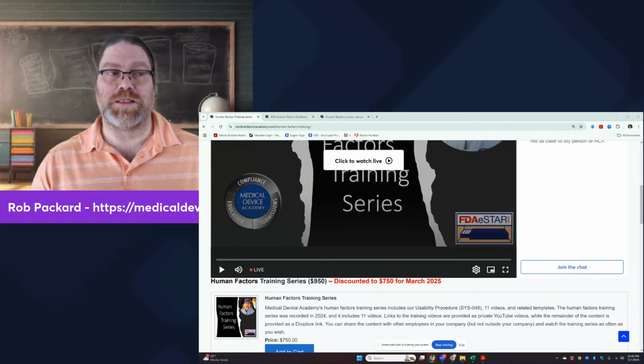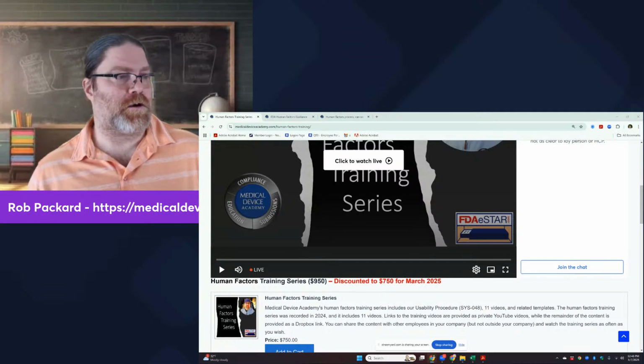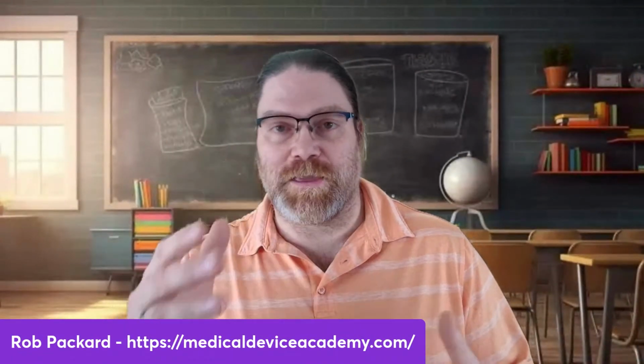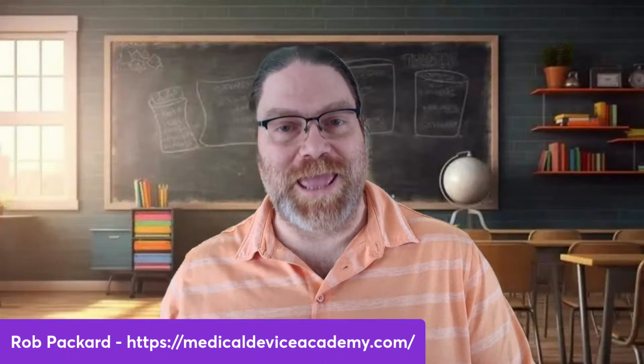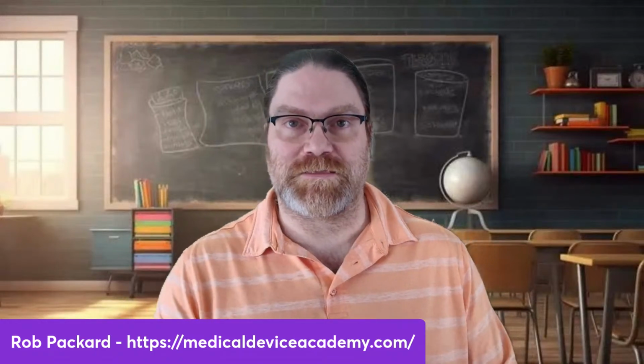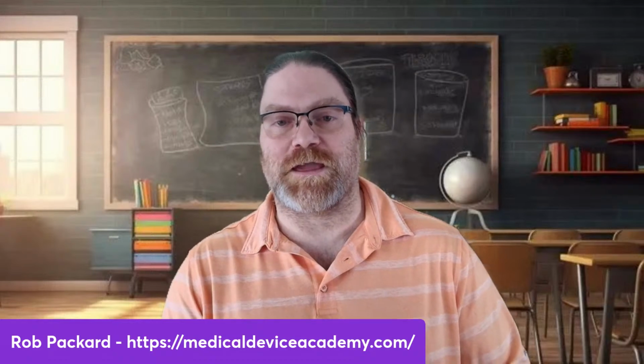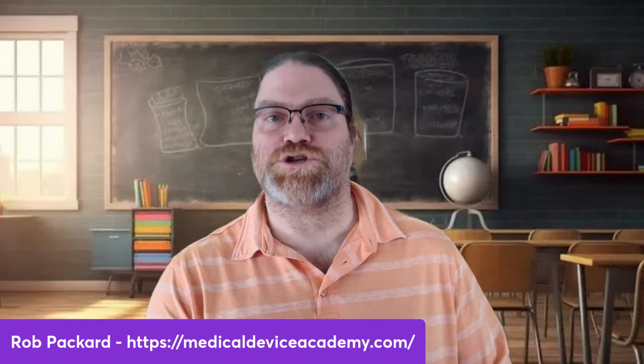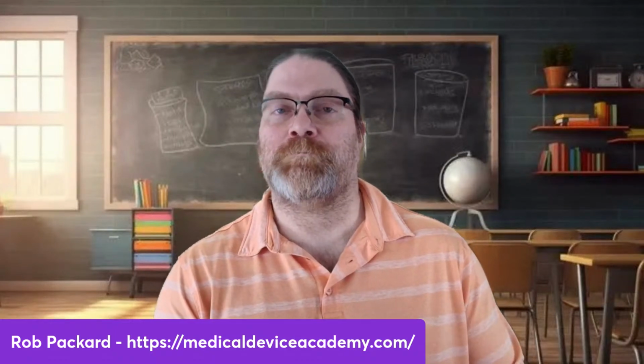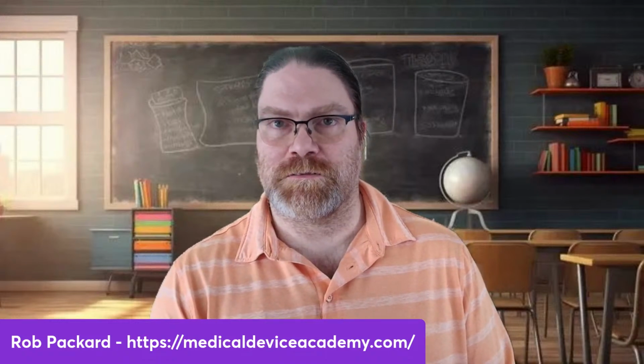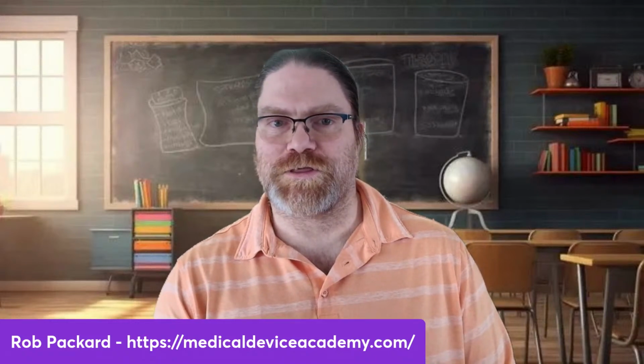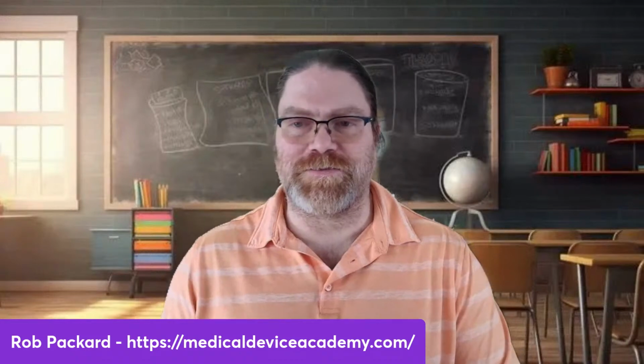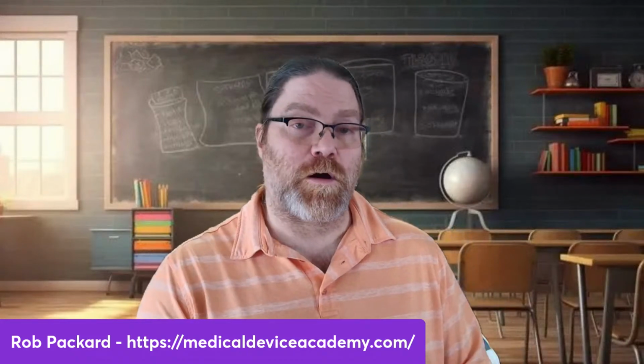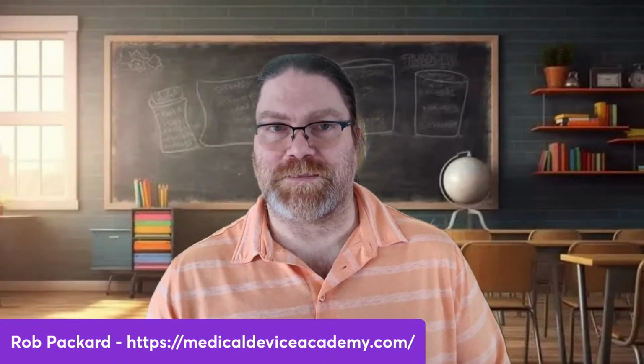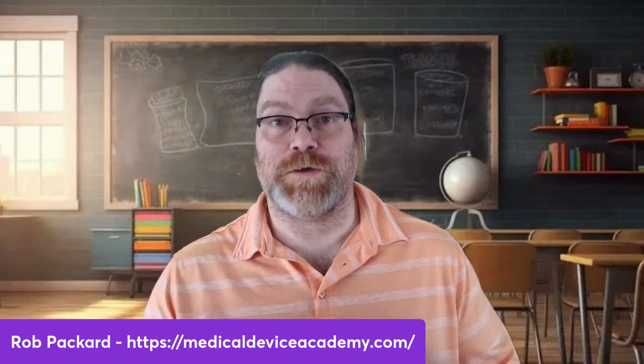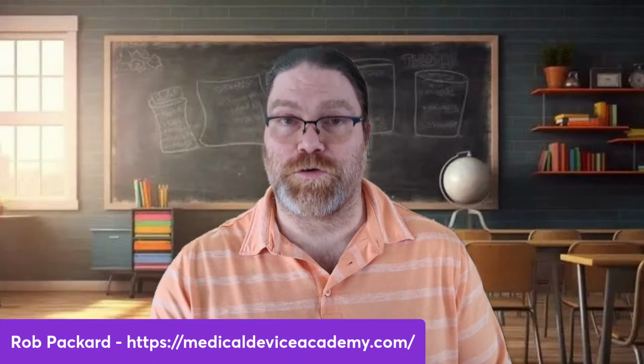So one of the questions we like to include at the end of an interview with any subject that's involved in a summative usability study is: is there anything in the instructions that wasn't clear, that could be improved? Any suggestions? Anything that was difficult to understand? Those are questions we ask at the end of the summative testing. We don't ask it before because we don't want to bias them. We don't ask them during because we don't want to interrupt the flow of the use case.